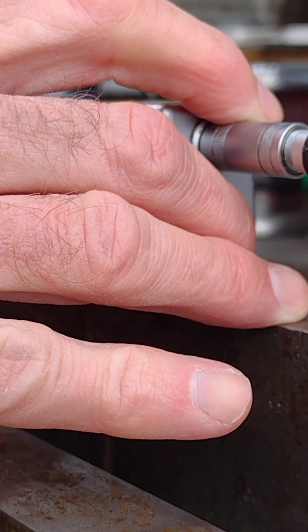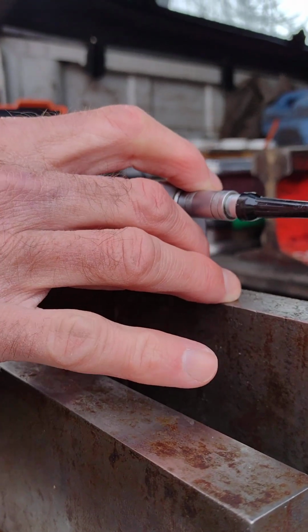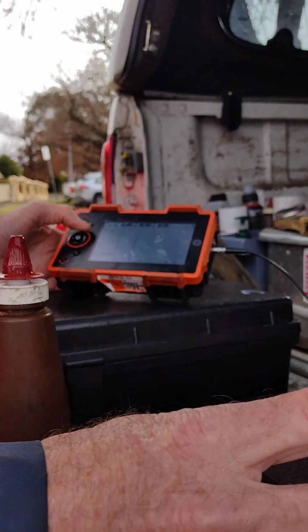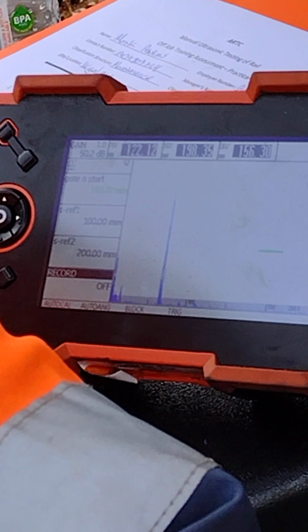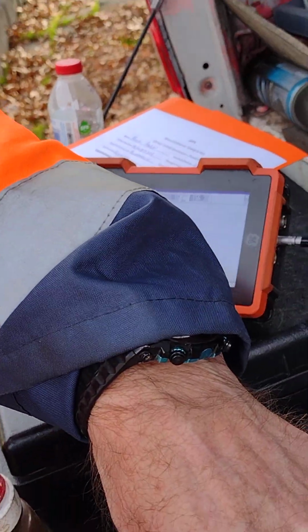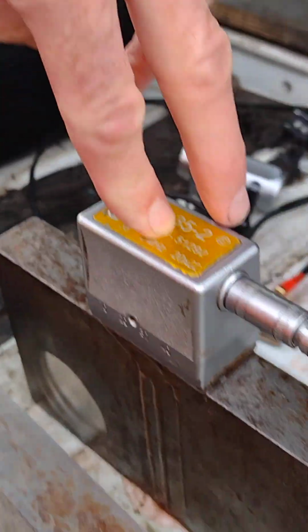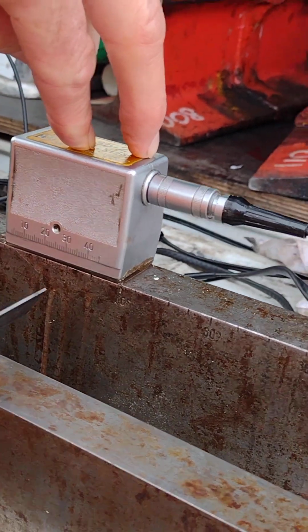on the screen. The gate is not important on this particular part of the process. We've just got to make sure we maximize the peak, and if the peak goes off the screen, bring the volume down or your dBs down till you find where the peak maxes out.